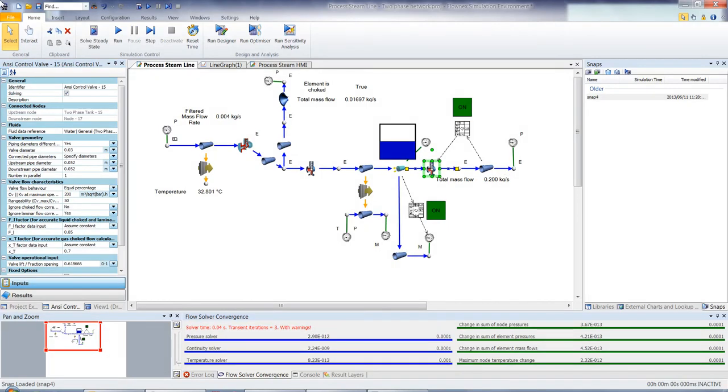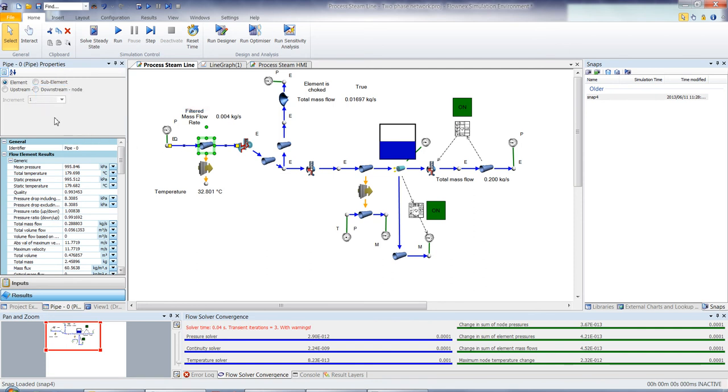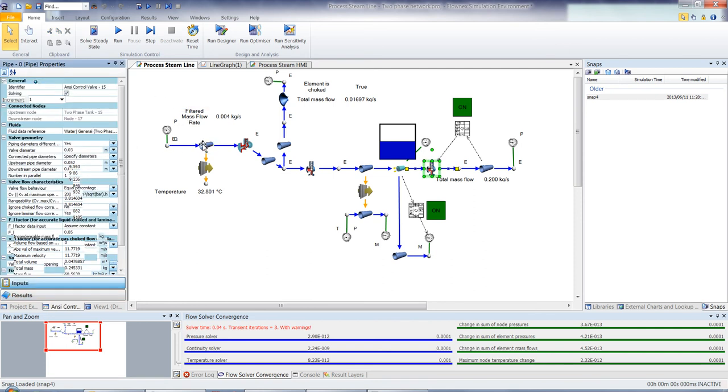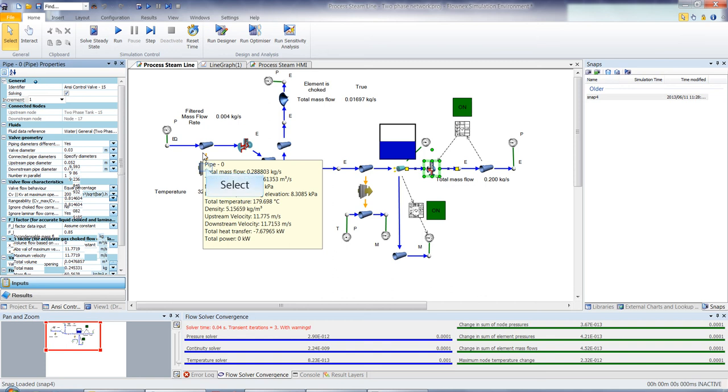Okay, let's have a look at the 100-meter pipe at the inlet where we're modeling heat transfer to atmosphere. Within this pipe, we have the ability to model a single component and then increment it. So in this case, we have 10 sub-elements. So this 100-meter pipe is incremented into 10 pipes with the mean properties over the length. So now we can get a distribution of density, pressure, quality changes within that pipe over its length.